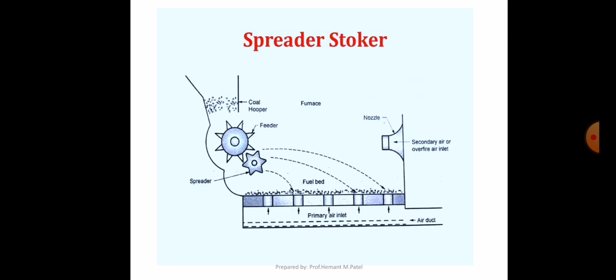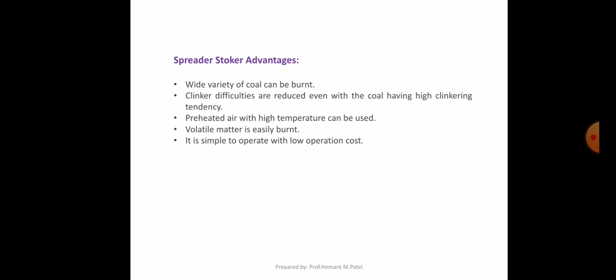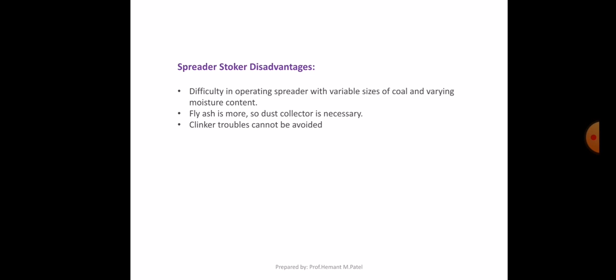Now we are talking about the advantages of spreader stoker. First, a wide variety of coal can be burnt, so we can utilize a variety of coal in the spreader stoker. Clinker difficulties are reduced, even with coal having high clinkering tendency. Preheated air with high temperature can be used. Volatile matter is easily burned. It is simple to operate with low operation cost. So these are the advantages of spreader stoker. Now the disadvantages of spreader stoker. There is difficulty in operating the spreader with variable size of coal and varying moisture content. Fly ash is more, so a dust collector is necessary. Clinker troubles cannot be avoided.